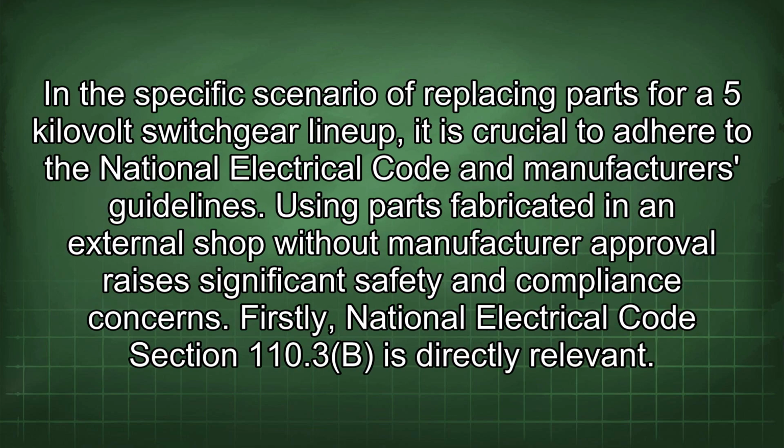In the specific scenario of replacing parts for a 5 kV switchgear lineup, it is crucial to adhere to the National Electrical Code and manufacturer's guidelines. Using parts fabricated in an external shop without manufacturer approval raises significant safety and compliance concerns. Firstly, National Electrical Code Section 110.3b is directly relevant.